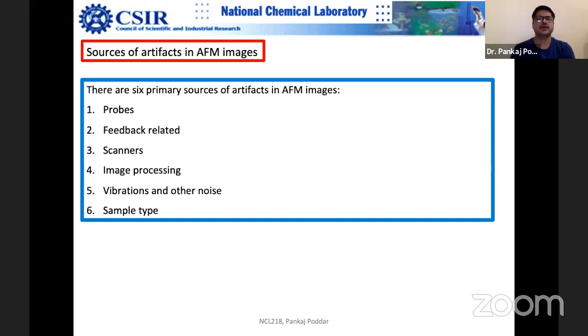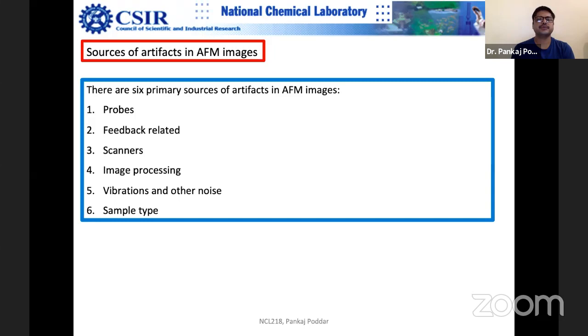We'll study what kind of artifacts can be created in various conditions due to AFM probes. The second problem is with feedback. The feedback given by the controller controls the fine movements of the scanner — whether the scanner should move up or down when it traces the topography of the sample. There is one parameter called gain. Sometimes gain is too high, which can introduce a lot of artifacts in AFM images.